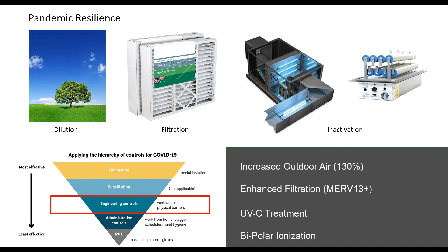Dilution with increased outdoor air - a lot of our projects have 30% increased outdoor air, initially for improved air quality and reduced CO2 levels, but this is also one measure against pandemics. Filtration is one of the most promising things; I'm excited to see a higher level of filtration quickly becoming standard, and it seems to have a small energy impact. Additional measures like UVC in the ductwork, air handlers, heat pumps, as well as bipolar ionization, are promising technologies we've been using increasingly.